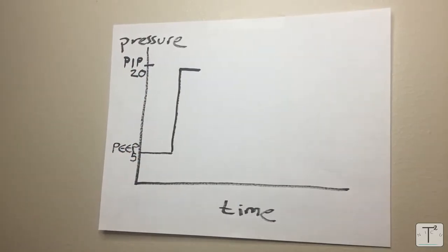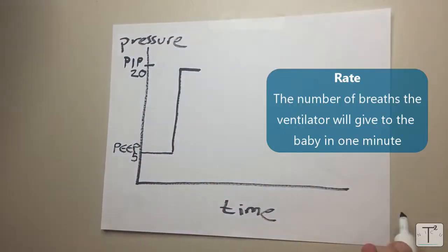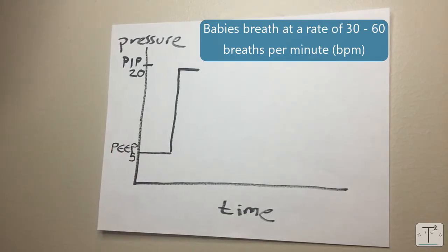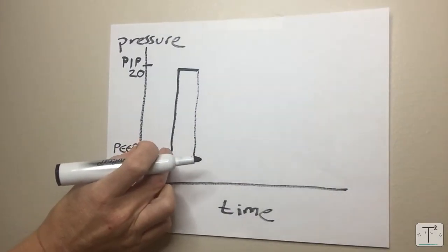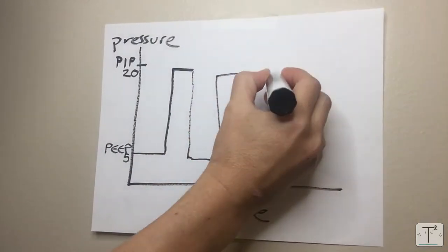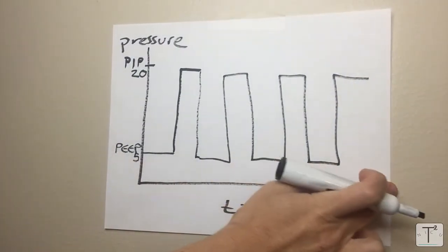The next thing you need to decide on your machine is what the rate of breaths that you're giving is going to be or how many breaths is the machine going to give in one minute. Babies breathe faster than adults between 30 to 60 times a minute. So if the rate is 30 then there'll be 30 breaths in a minute or one breath every two seconds. One breath would be taken up by a PEEP and a PIP so that would be considered one breath. So then we have another breath here, another breath here, and another breath there, so on over the course of a minute.